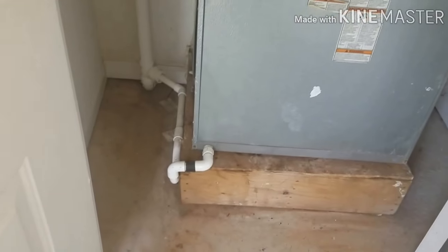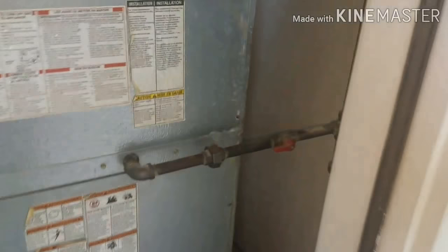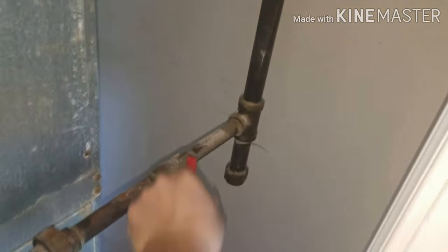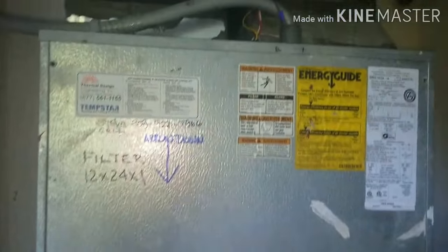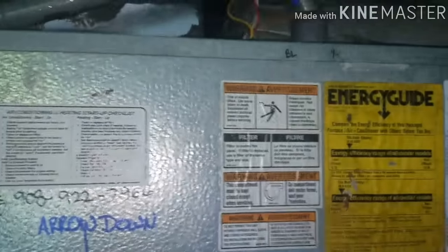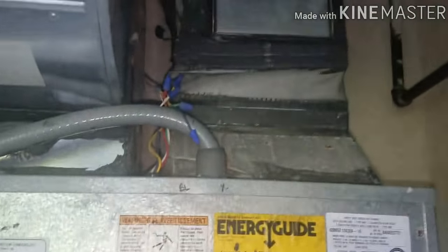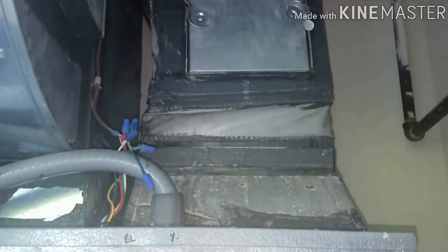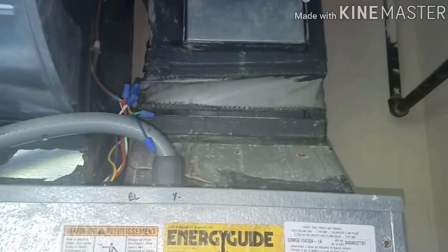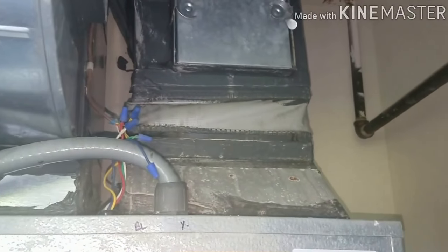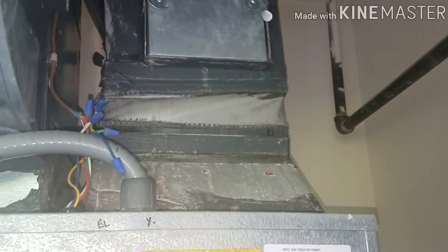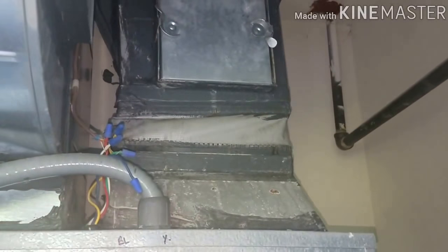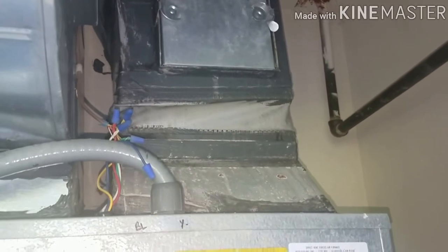So you got your little drain right there, got your gas pipe, electrical, low voltage. All these units have these fire dampers on the supply and return, which have a fusible link, and if that link gets too hot and melts — I forget what degree, like 180 or 208 or something — the damper will close.